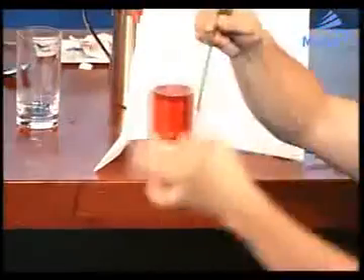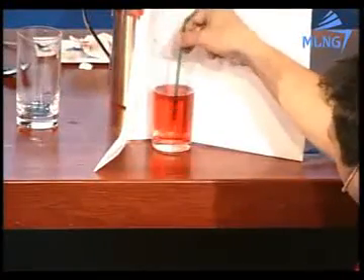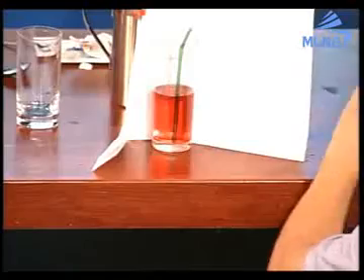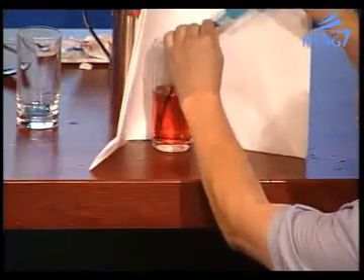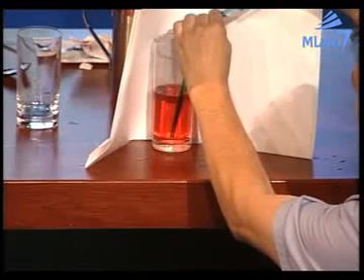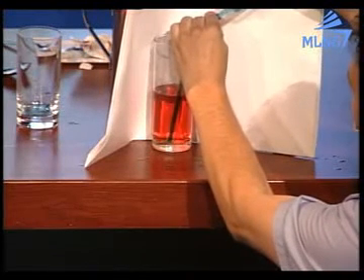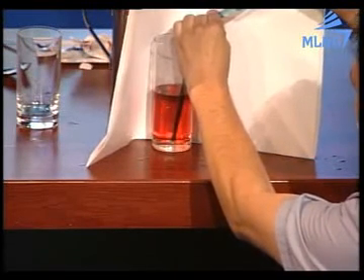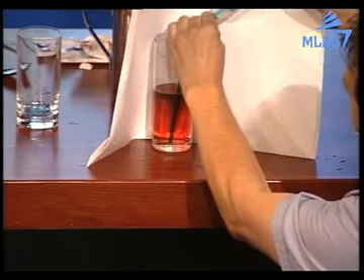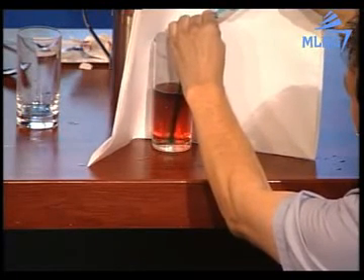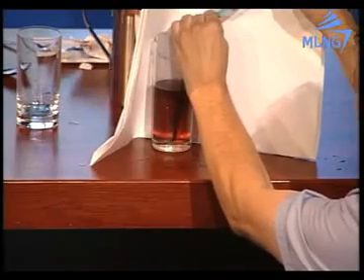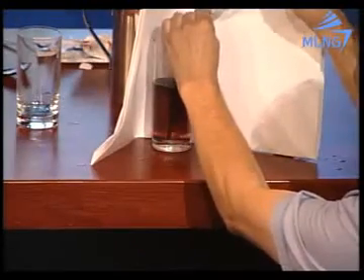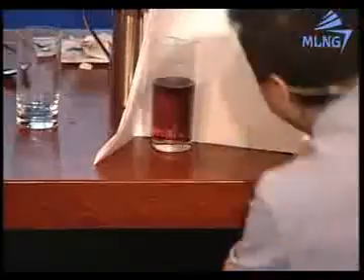Well, this is the bottom line or downcomer. Okay. So I want you to see that it's homogeneous and how the blue liquid goes up and mixes itself. Do you see that? So this is the best way of filling up a tank, avoiding stratification. Okay? So, sirs, now we have a safe tank.